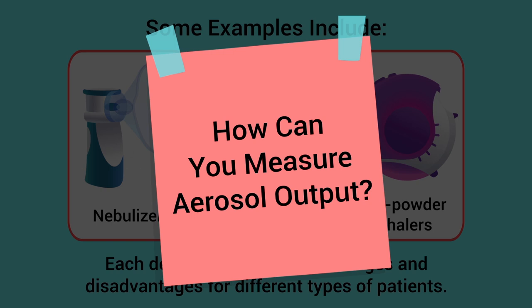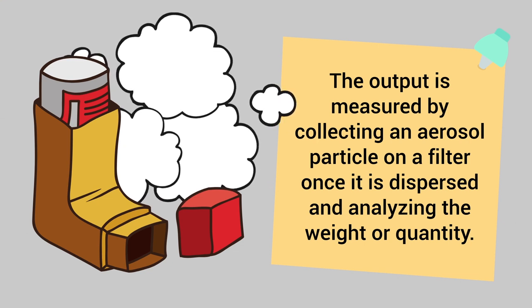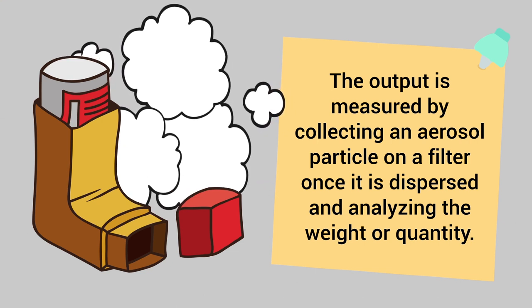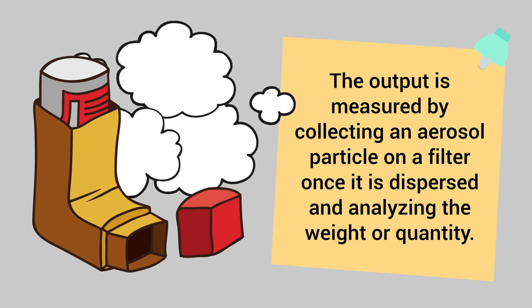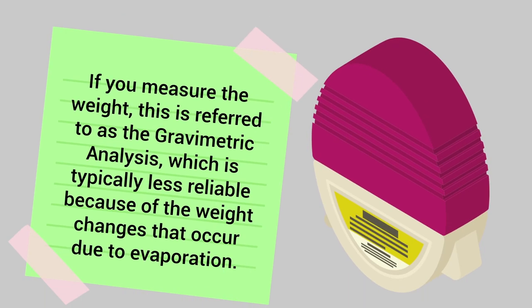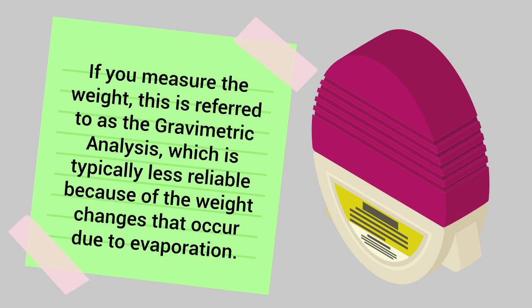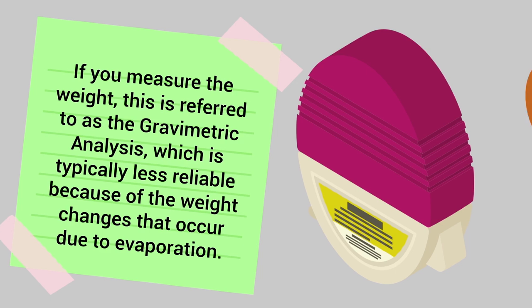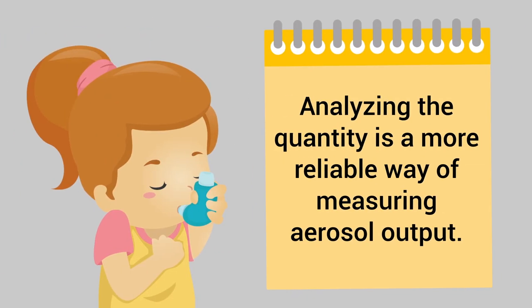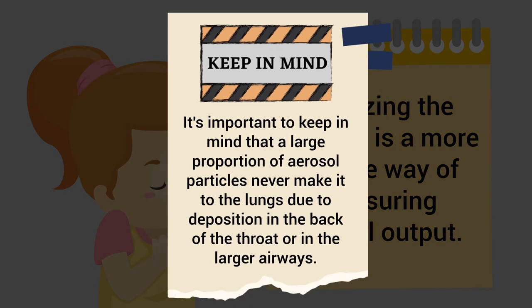Aerosol output is measured by collecting an aerosol particle on a filter once it is dispersed, and then analyzing the weight or quantity. If you measure the weight, this is referred to as gravimetric analysis, which is typically less reliable because of the weight changes that occur due to evaporation. Analyzing the quantity is a more reliable way of measuring aerosol output.